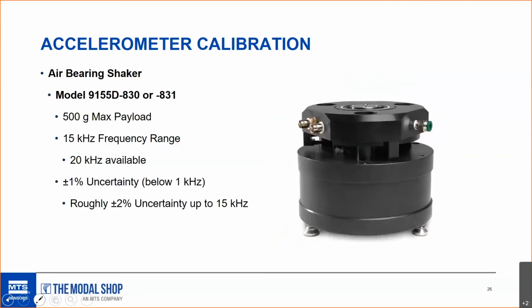All right. The air bearing shaker from PCB and the Modal Shop has a 500-gram max payload, not quite as much as the PVC. It has an extended frequency range and is really used for test and measurement sensors, but it's part of a larger system that will deliver plus or minus 1% measurement uncertainty, which is a slightly different unit of precision than the accuracy that Mike states for the PVC. Once you get up to 15 kilohertz, it's roughly plus or minus 2% measurement uncertainty for a coverage factor of 2. But we're not going to go into all the statistics and how they are done to get those values. That's part of our larger laboratory system.